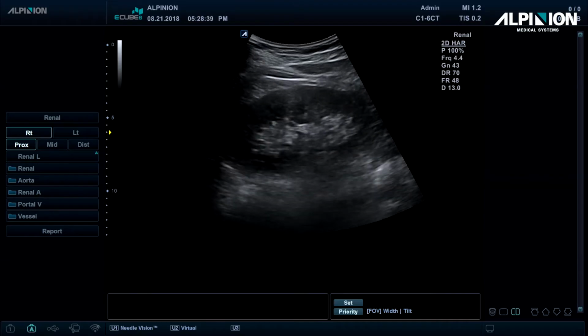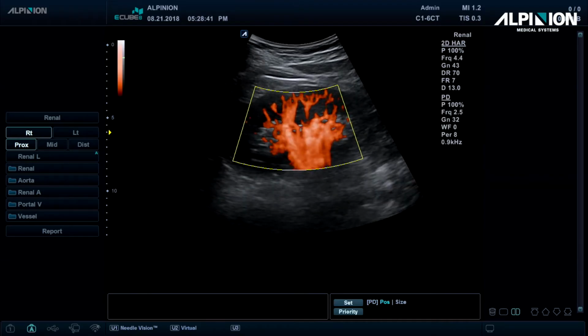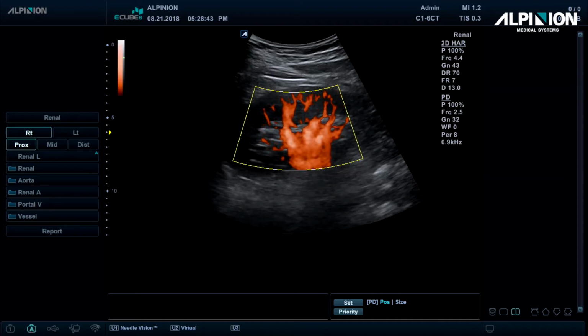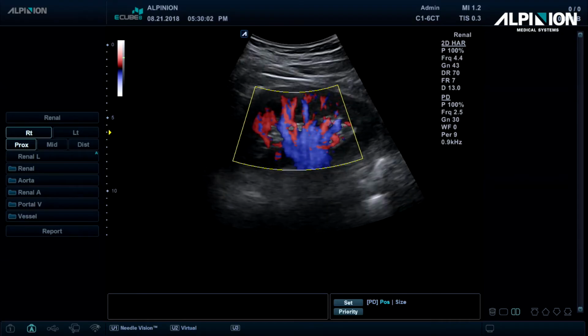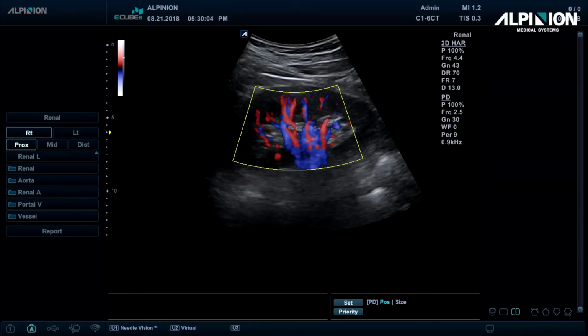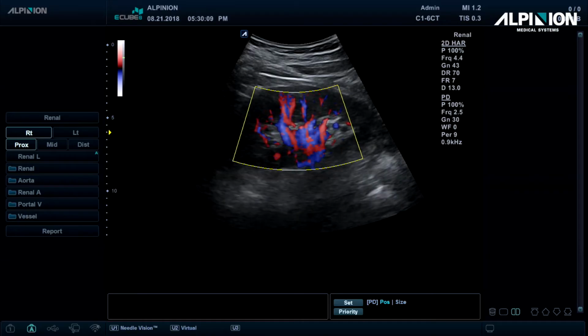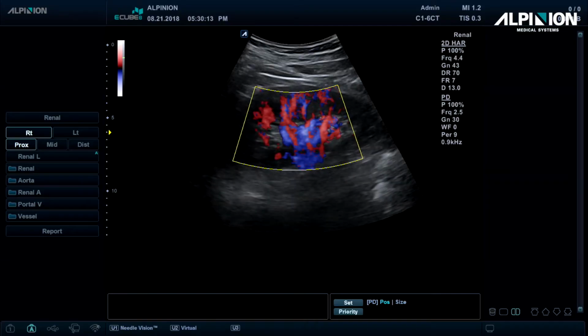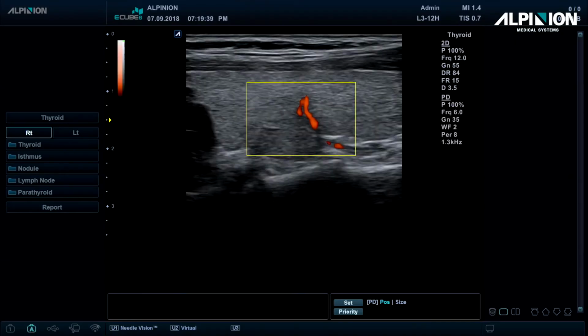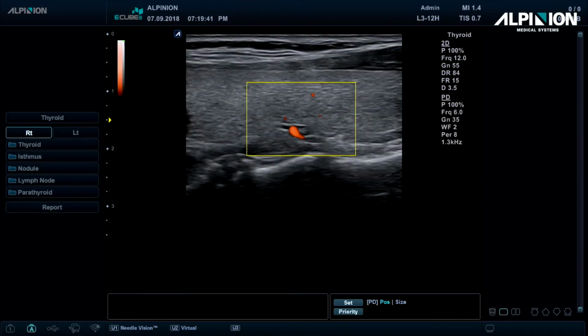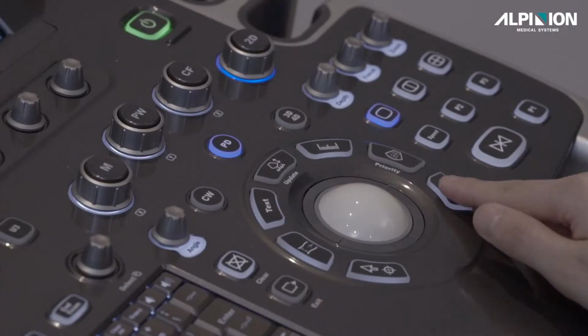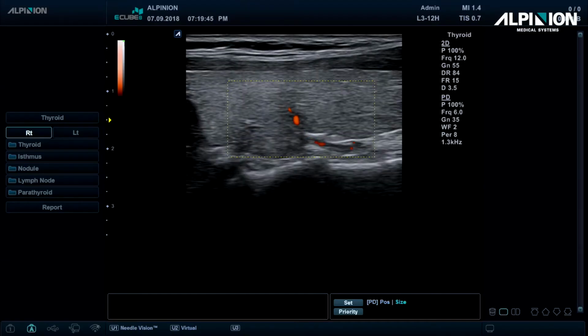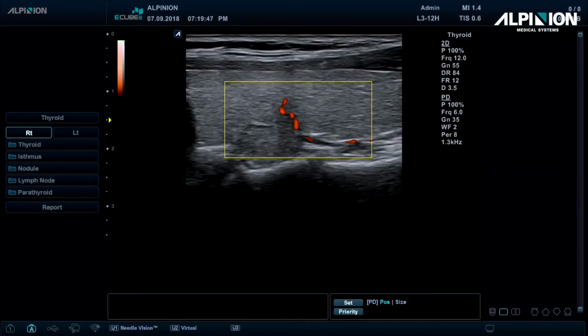Part 11. Power Doppler Mode. Power Doppler mode is another Doppler mode that has more sensitivity than the conventional color Doppler for detection of flow and is particularly useful for small vessels. And our DPDI mode stands for Directional Power Doppler Imaging mode that combines the advantages of both Dopplers by providing the directional information of flow with higher sensitivity. Once you press the PD button here, you can activate Power Doppler mode. With your Set button, you can change the box size to cover your ROI and move it with your trackball.